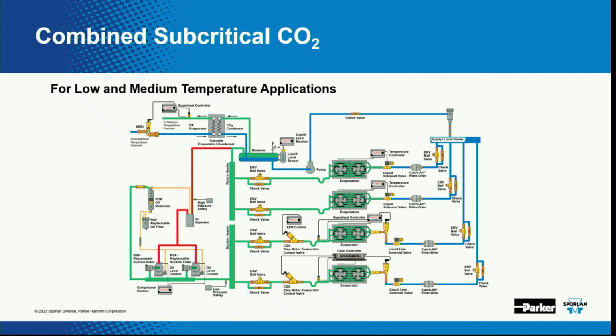But down here on the bottom is our low temp, and these require compression to get that additional drop. Basically I've got the same liquid, common liquid line, common liquid header, and these require actual expansion valves. Then when it comes out of suction, it goes back into compression, compresses it back up, and puts it back into the receiver there. So that's just a combination.